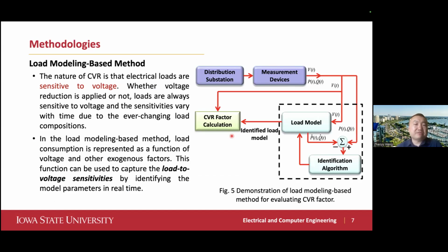That means the nature of CVR is that loads are sensitive to voltage. If the load is not sensitive to voltage, when you reduce the voltage, what would happen? Let's consider the extreme case: all the loads are constant power loads. When you reduce the voltage, what happens? Your total consumption will go up.